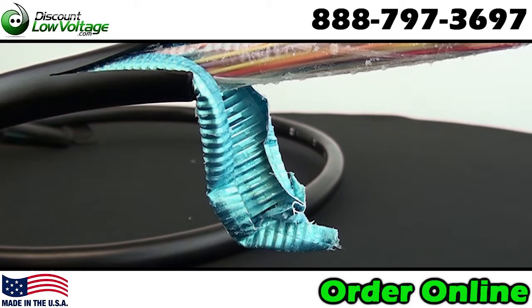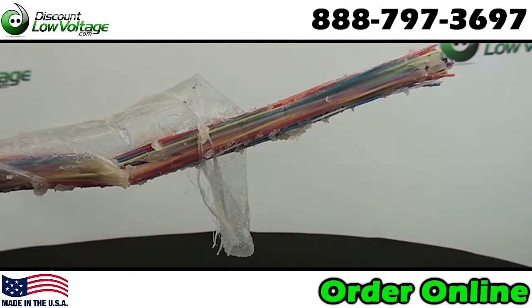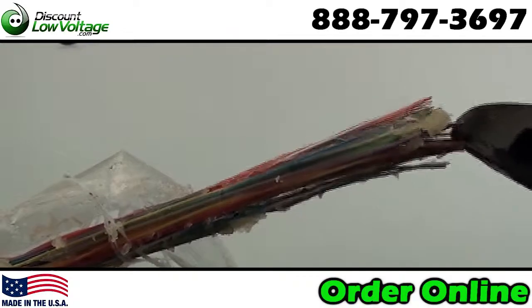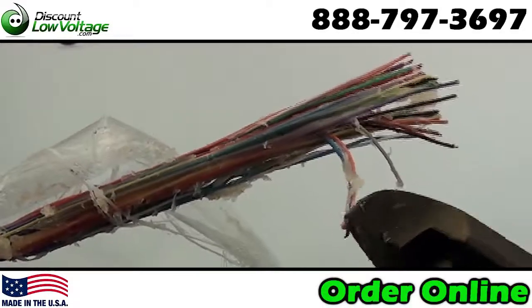Conductors are twisted into pairs with varying lay lengths to minimize crosstalk. This cable does have a filling compound and it intersects between the pairs and under the core tape. You also have an aluminum shield.